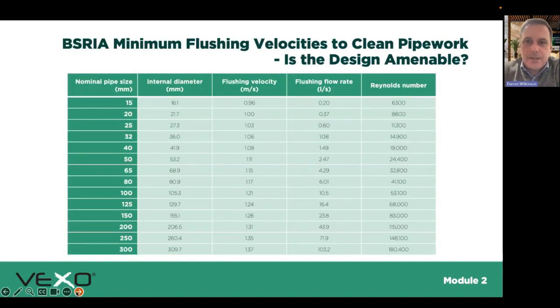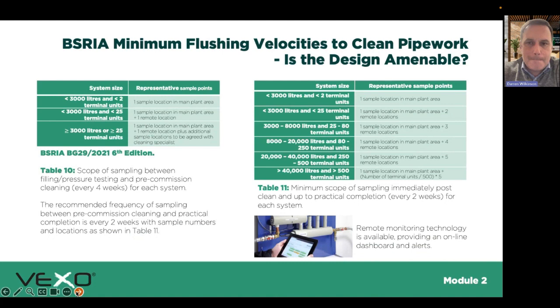Going back to BSRIA, they provide information on what you'd expect your flushing contractor to achieve in terms of velocity, dependent on pipe size. So as you design systems and look at the flow rate you want to achieve at design, take a quick look at the BSRIA guide and ask, could we get up to that? Because there are systems that have been ultra low flow, almost impossible to clean. All of this is available in the BSRIA guide.